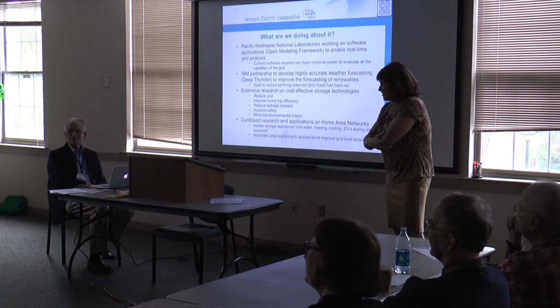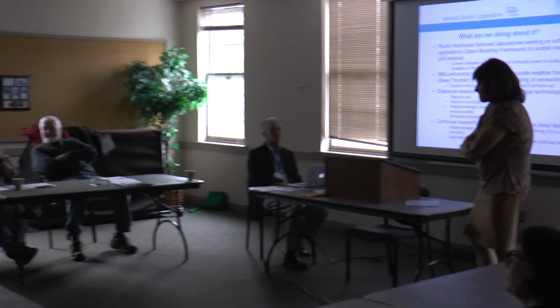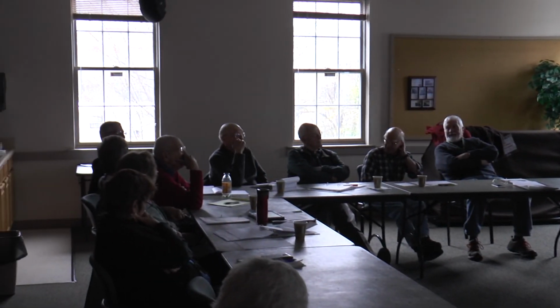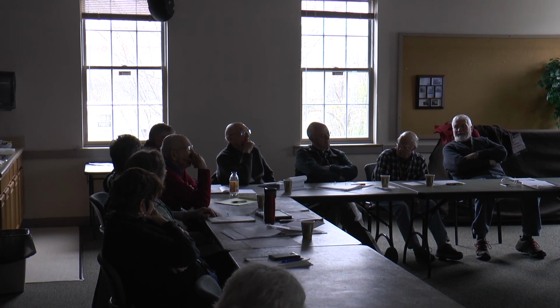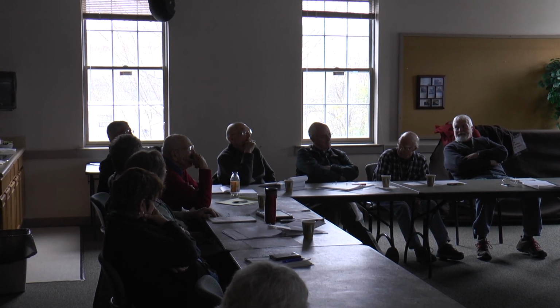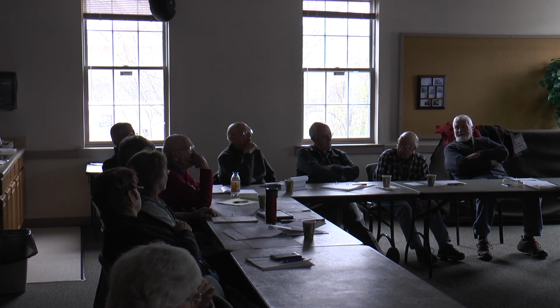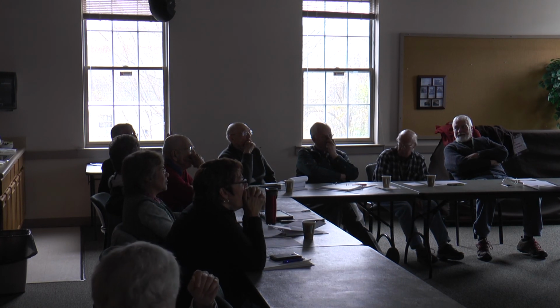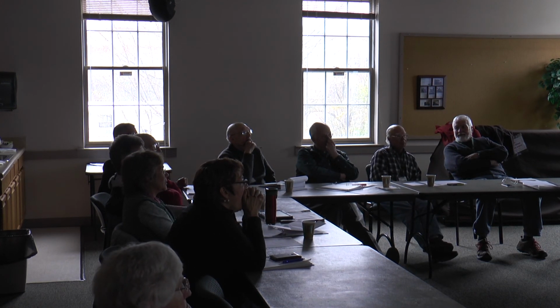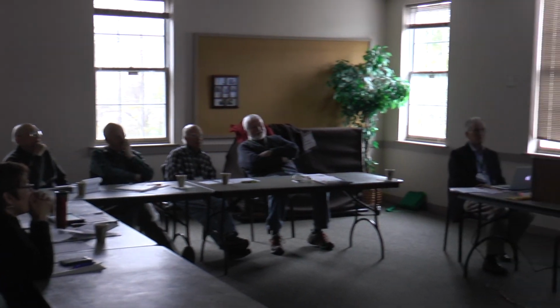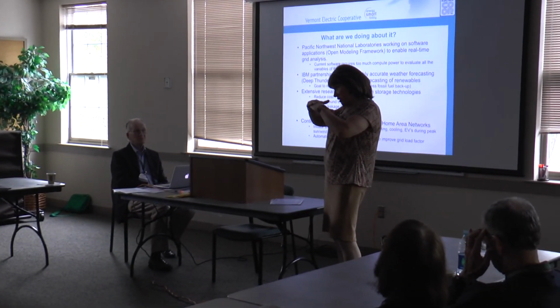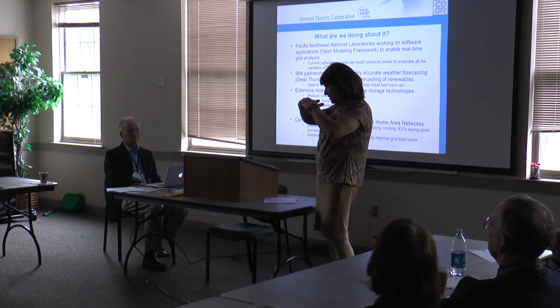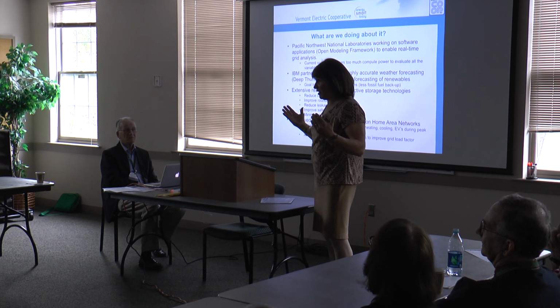Yes, you have a question? On one of the slides with the supply mix, the trend for solar was definitely going up and hydro was going down, natural gas was going way down. Yes. So assuming a 10 or 20-year trend, it almost looked like natural gas would be zero and solar would be 30% in the next 10 years. Well, we can't get there because of all the electrical issues. The point is, in Vermont, at least on our grid, we've really started to approach our limits. Until we figure out the electrical stuff, we can't put any more on.